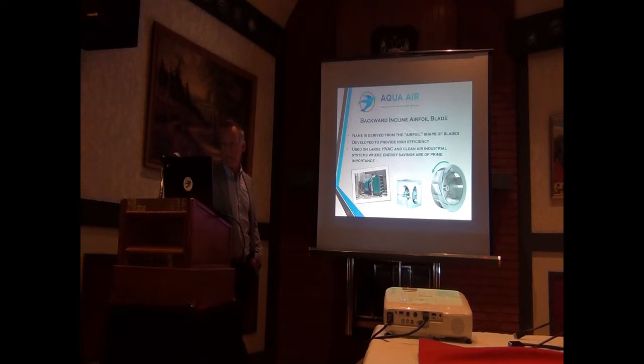So these are developed to provide high efficiency, like we said, in the 80–85% range, and are used on large HVAC and clean air industrial systems where energy savings are of prime importance. If you look here, a backwards inclined fan and a forward curve fan often came in that traditional housing. With the backwards inclined airfoil fan, you can see this plenum fan arrangement that became very popular. It's a pressurization fan. We'll talk about some of the advantages there, but it was another improvement in the efficiency of how we move air.